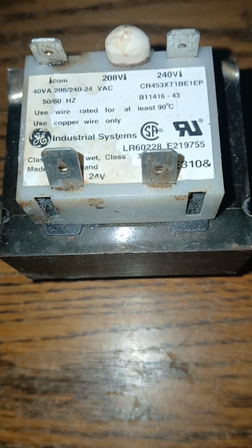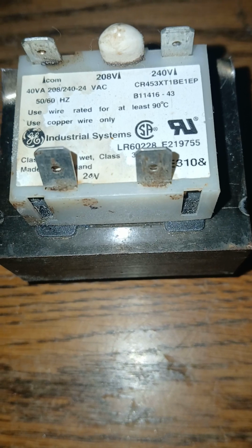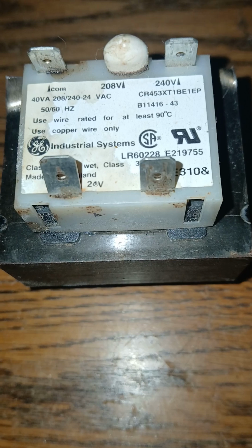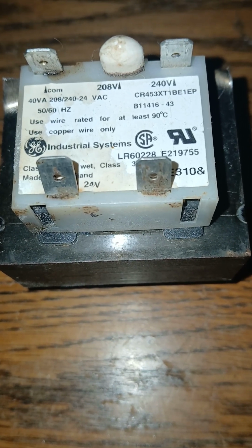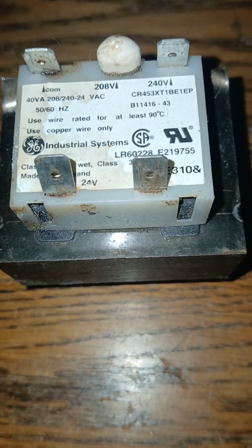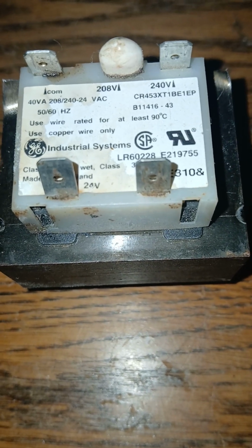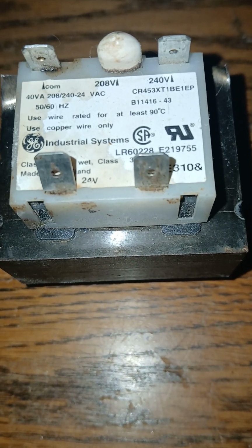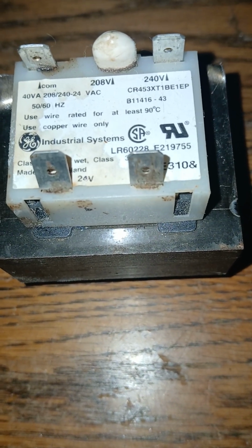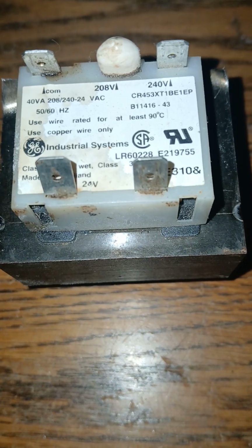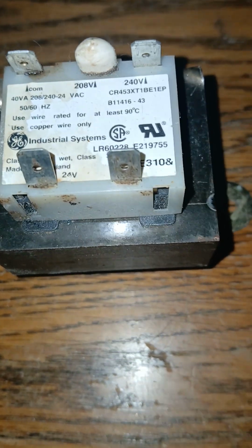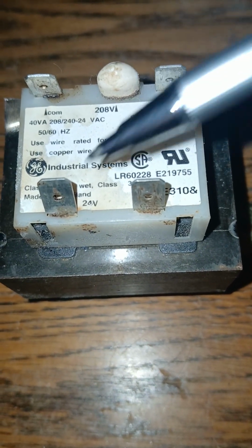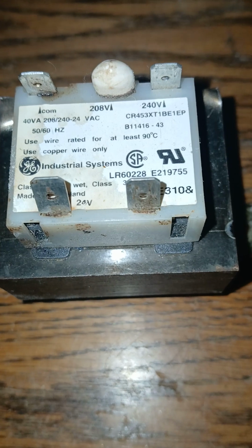How often do these go bad? My opinion is rarely do they go bad. Anything's possible. If one touches the common wire and the hot wire, maybe while changing the thermostat, they could potentially blow this transformer if there's not a fuse in line to break before it gets here. But generally speaking, I've rarely replaced any of these. I have replaced them, but it's not very often. So it's simply to take a high voltage and step it down to a low voltage.